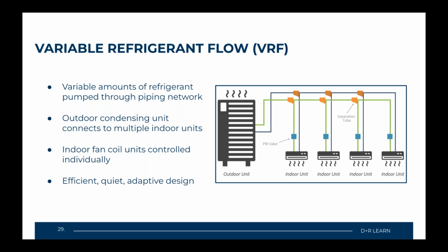But VRF systems have an outdoor condensing unit, typically one condensing unit connected to multiple indoor systems, as you can see in this diagram here. Variable amounts of refrigerant are piped from the outdoor unit to the indoor units, resulting in flexible load distribution. Now, VRF systems do require a lot of refrigerant to be piped through a building, but they can also save a lot of space that would otherwise be lost by a huge amount of ductwork for traditional hydronic systems. But the refrigerants can pose challenges with code, especially if dealing with a leaking system in an occupied space that could really get you in trouble, or it could halt operation until you're able to find that leak. But the ultimate design of these VRF systems can be flexible and utilize wall ceiling or the ducted type of cassette installation for your indoor systems.